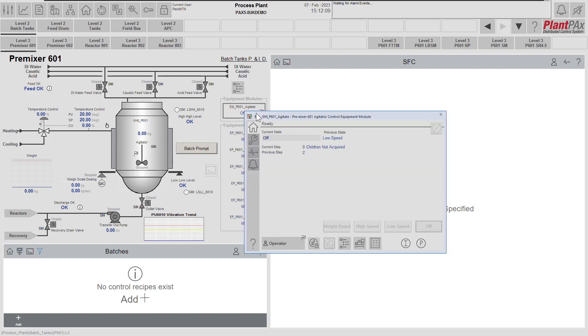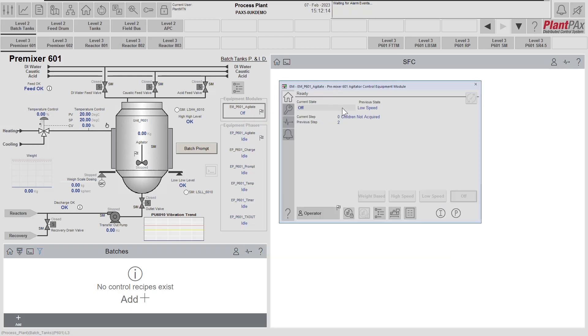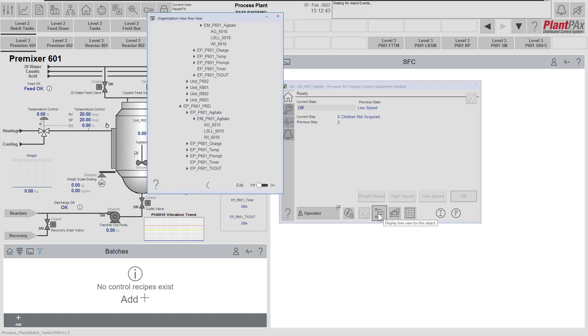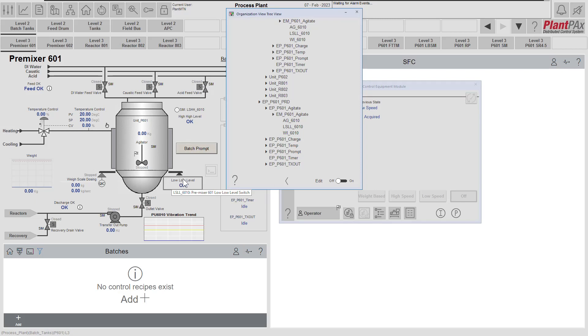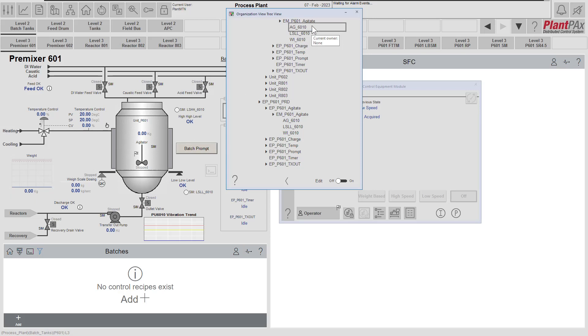When we click on that it brings up the equipment module faceplate. The equipment module has four different states: off, low speed, high speed, and weight based. When those states are available to be entered and exited is all configured in the logic for the equipment module. The equipment module uses some of the PlantPAx instructions it monitors and controls, and those can be seen from the organization ownership and arbitration tree view. This equipment module uses the agitator, monitors the limit switch, and also uses the weight of the pre-mixer for controlling the agitator in weight-based mode.